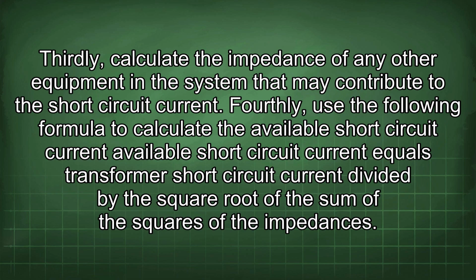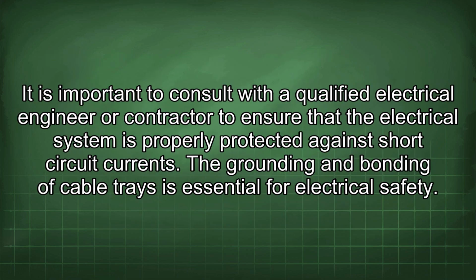Available short-circuit current equals transformer short-circuit current divided by the square root of the sum of the squares of the impedances. It is important to consult with a qualified electrical engineer or contractor to ensure that the electrical system is properly protected against short-circuit currents.